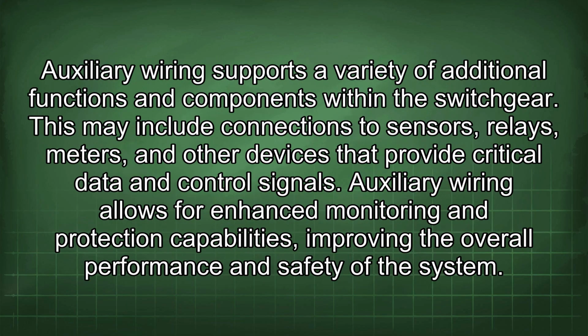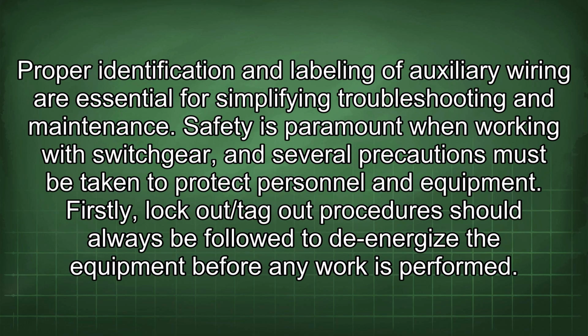Auxiliary wiring supports a variety of additional functions and components within the switchgear. This may include connections to sensors, relays, meters, and other devices that provide critical data and control signals. Auxiliary wiring allows for enhanced monitoring and protection capabilities, improving the overall performance and safety of the system. Proper identification and labeling of auxiliary wiring are essential for simplifying troubleshooting and maintenance.